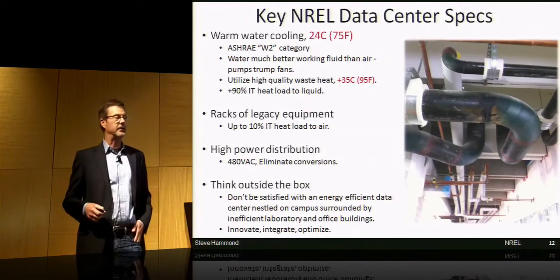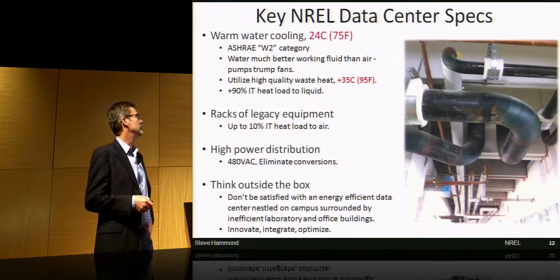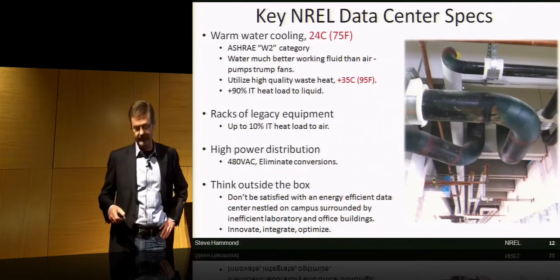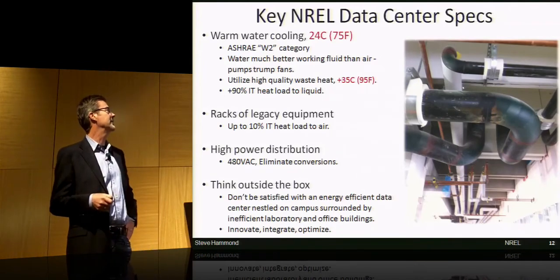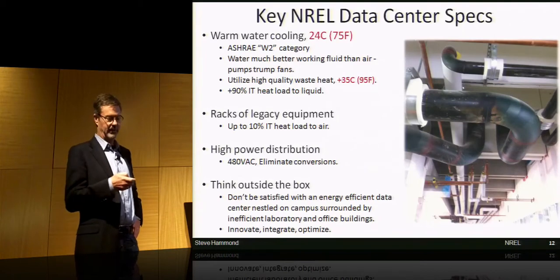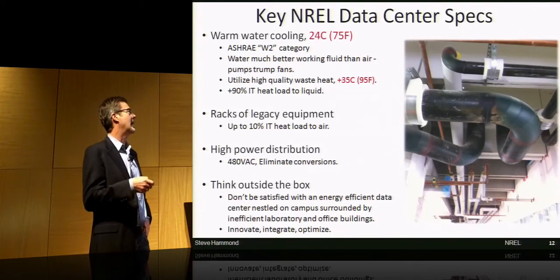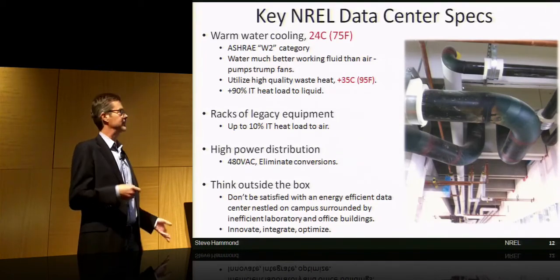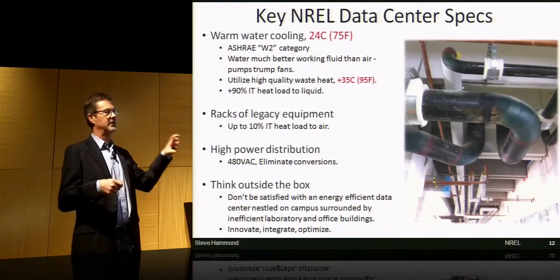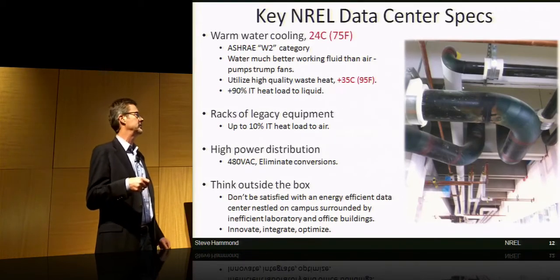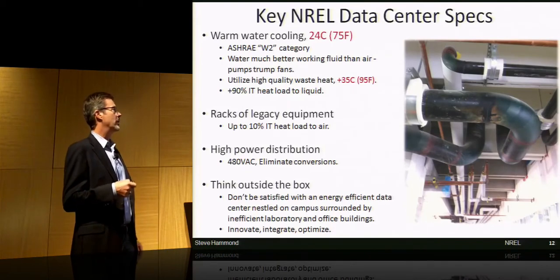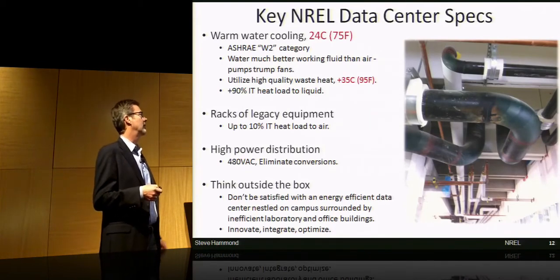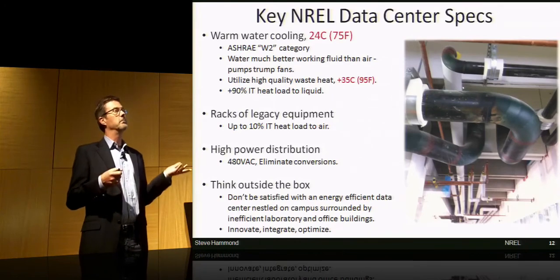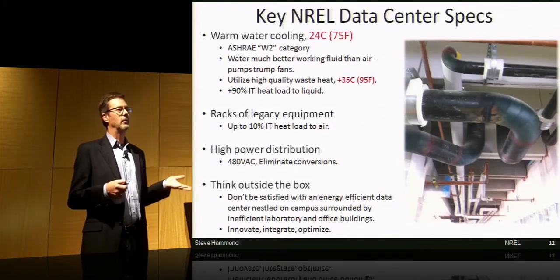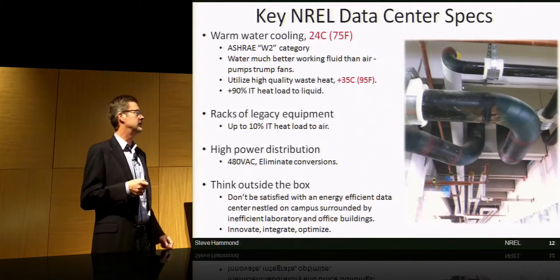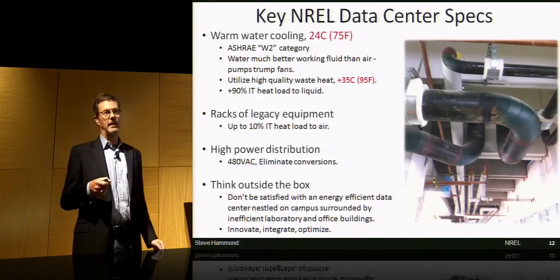Some of our key data center specs: as I said, we do have warm water liquid cooling. Mike Patterson cringes every time I say that—he wants to remind me there are actual classifications. So we are an ASHRAE W2 classified data center, which specifies our supply temperature range. Water is a much better working fluid than air. As built, it's a 2 megawatt facility with room to expand fully to 10 megawatts.